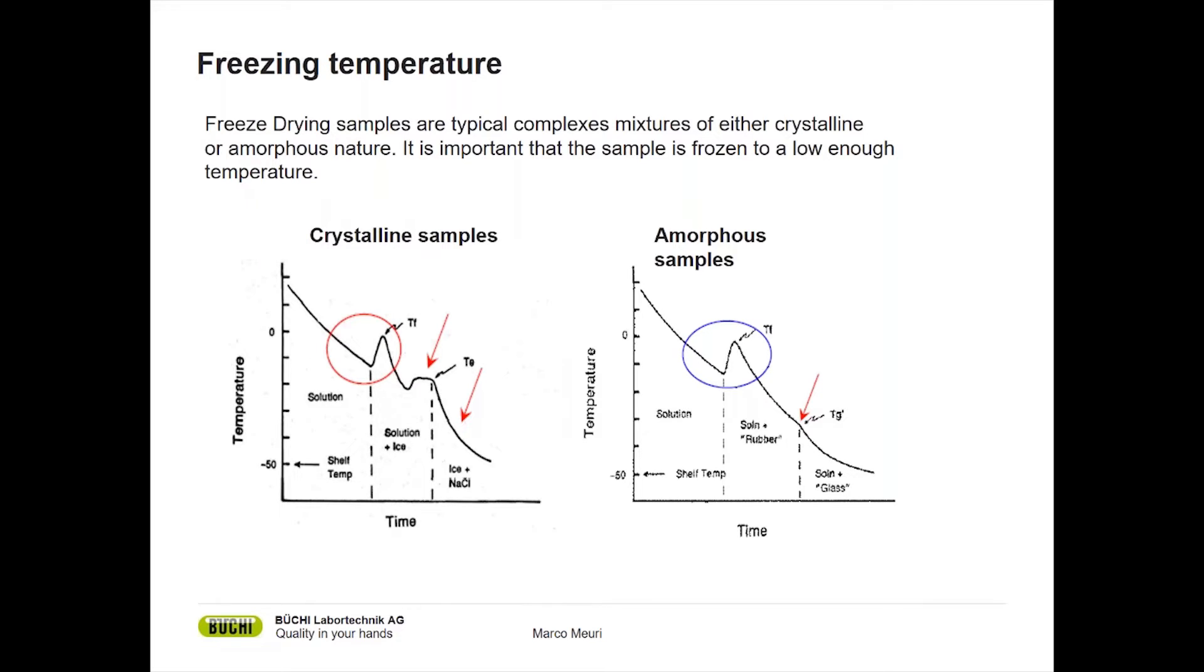If we look at the example of a crystalline sample, water and salt, if we freeze this sample you can see in the graph on the left side we first go down in temperature, then we go to an area called super cooling. That means the sample goes even below its freezing point. Then first crystals will be formed, the temperature slightly increases again and the sample crystallizes. It forms ice. This small peak we can see here is the freezing temperature of the sample.